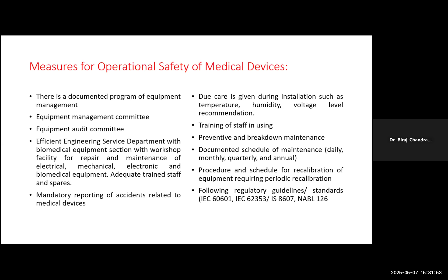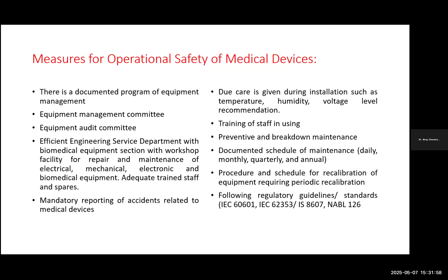Then the procedure and schedule for recalibration of equipment requiring periodic recalibration. Usually we follow NABL 126. If you Google NABL 126, you will readily get the document with the time frames: which equipments, and how frequently you have to do the calibration, maybe 6 months or 1 year. It depends on multiple factors, but you can have a ready reference from that document, or you can refer to the Indian Public Health Standards, IPHS 2020. The most important thing is the recommendation of the manufacturer. Always follow the recommendations of the manufacturer or the NABL 126 document for scheduling of calibration. Following regulatory guidelines, we have to follow IEC 60601, IEC 62353, IS 8607 and NABL 126.